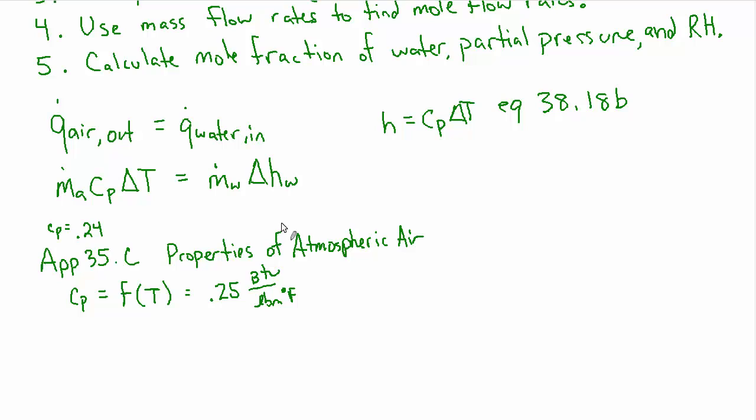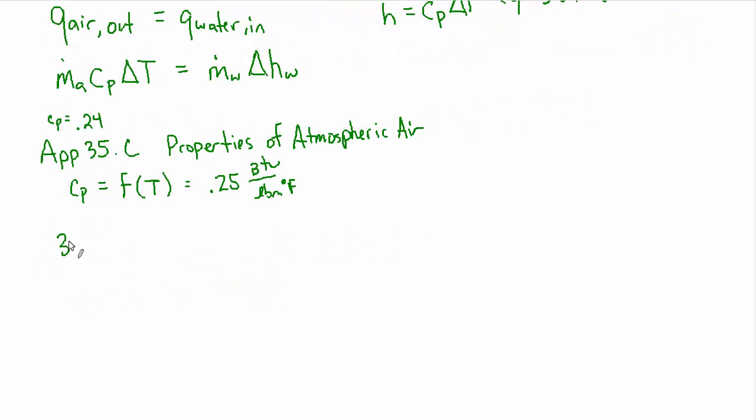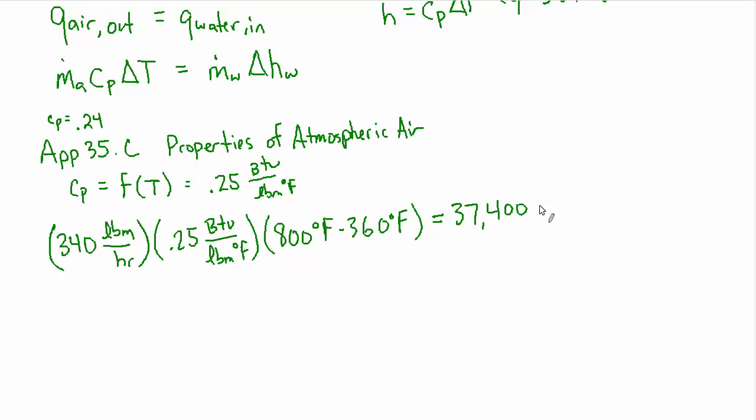So let's go ahead and do it. So the mass flow rate is 340 pounds per hour. CP we're taking as 0.25 BTU per pound. And the delta T is 800 degrees Fahrenheit minus 360 degrees Fahrenheit, which ultimately gives us a heat transfer of 37,400 BTU per hour. So that's how much heat is coming out of the air and thus going into the water.